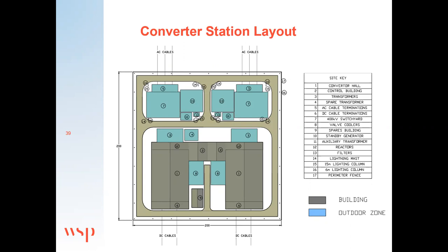So in this example, we put the transformers up against the building and put a lot of the equipment inside very large buildings. Primarily, we avoid a bit of noise. We're conscious that we're in an agricultural area, and audible noise from transformers and cooler fans would be a problem to what few neighbors there were. But still, nobody wants to hear transformers humming for the next 40 years. So we put transformers with noise shields, and most equipment inside buildings.